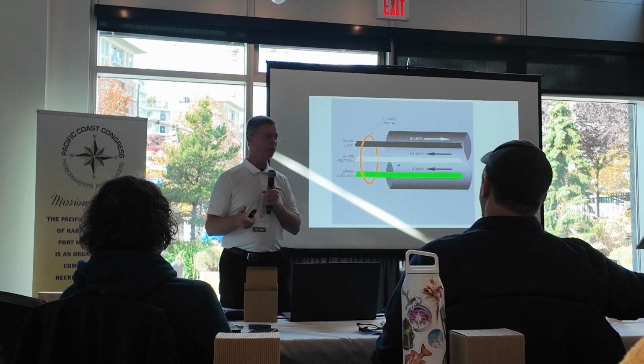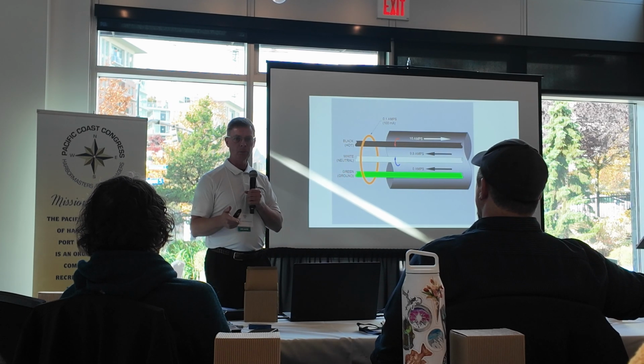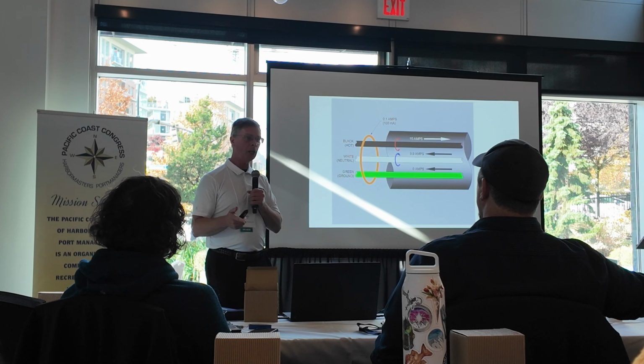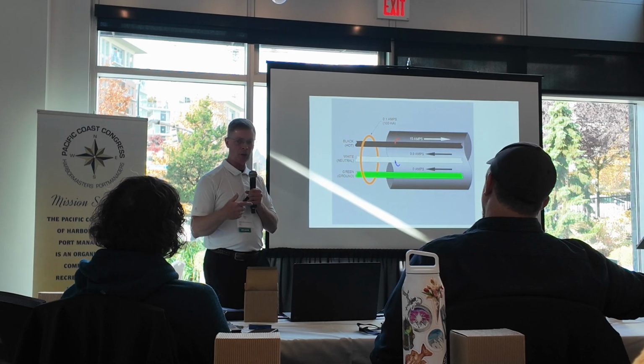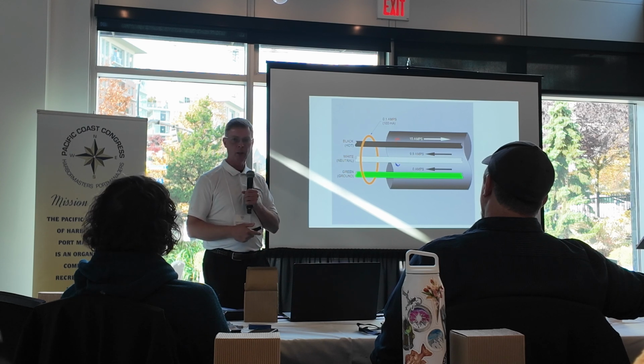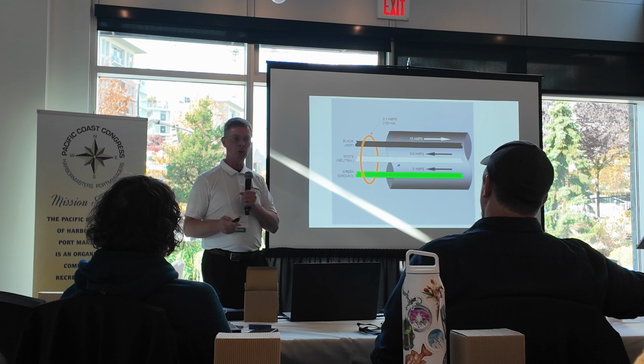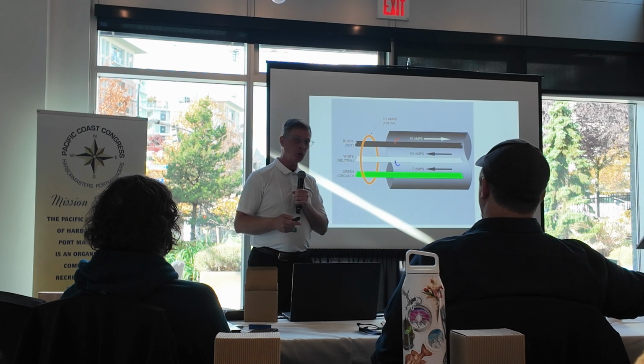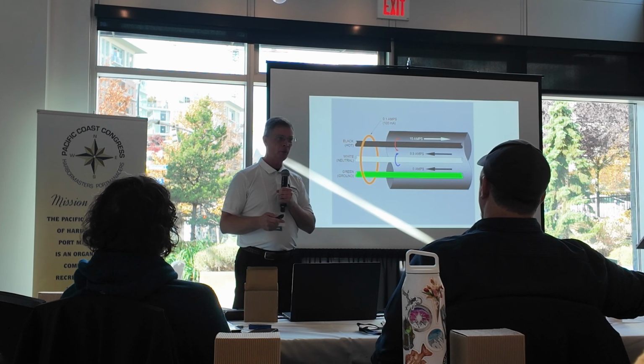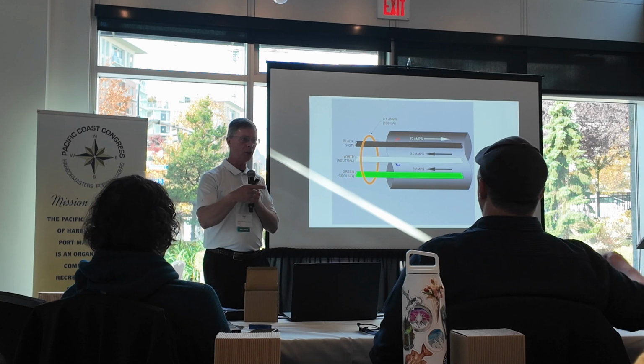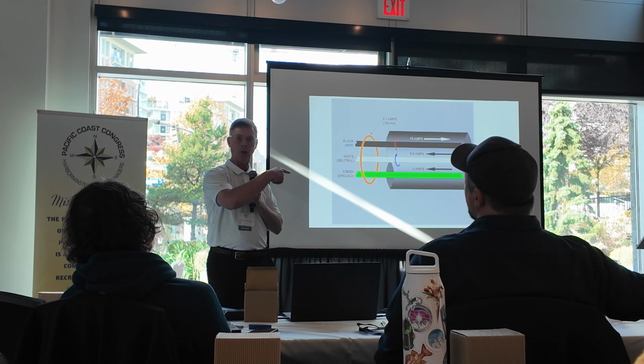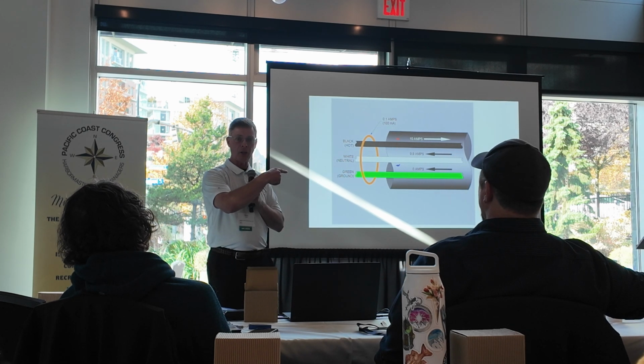So in a marina, what's the environment? Water. And there's a really good chance that 100 milliamps is not coming back on that shore power cord. It's coming through the water back to the source somewhere. And generally, what is the source? What is the source? No? Your feeder. Generally, it's the utility transformer. Okay? If it's a 240 volt system, it's the secondary side, it's the center tap of the transformer, which is back on where? Land. Yeah.